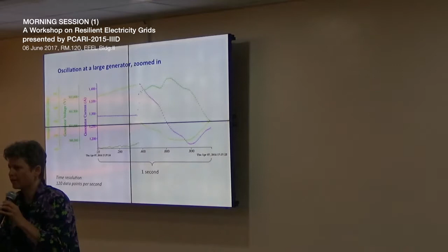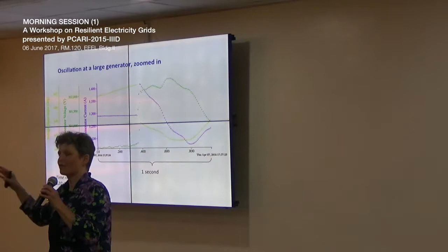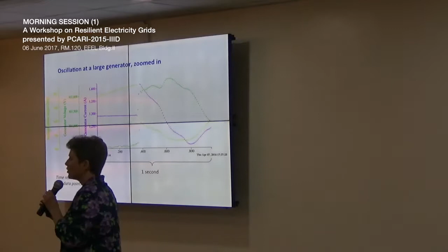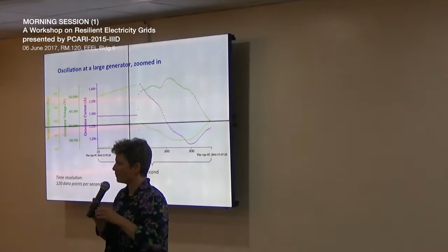Anything faster than that, and it doesn't make sense to report a phasor, because a phasor is a quantity that only is defined in the context of the 60 cycle waveform. So it's really only once or twice per wave that you can even talk about a phasor. You want to look closer than that, you have to look at the time domain, at the harmonics and the full waveform. But that then gives you information about the local electrical behavior and not about the long distance power flow that happens at the fundamental frequency.